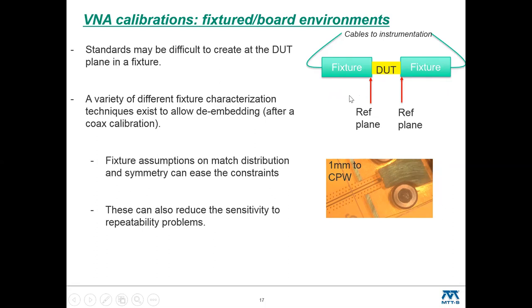One approach that's led to a number of different algorithms is to add assumptions about the fixture to reduce the stress on the standards at this reference plane. Those assumptions might be about symmetry, or about where the mismatch is located—for example, is it only at these launch points? Taking advantage of that information can reduce the stress on both repeatability and on what the standards have to do.